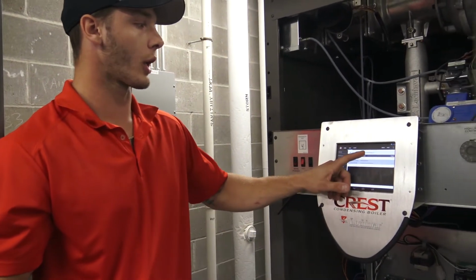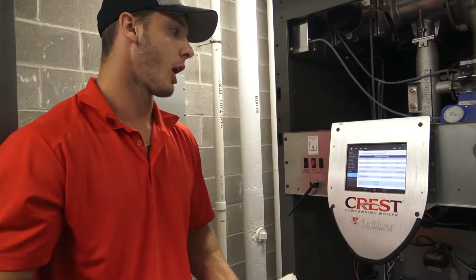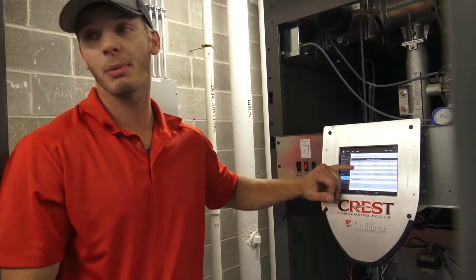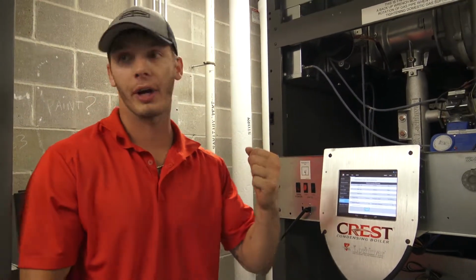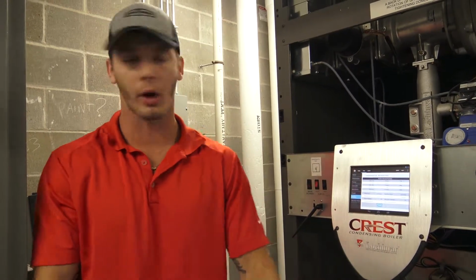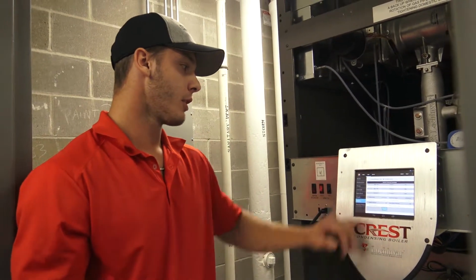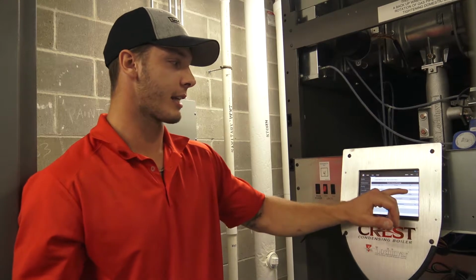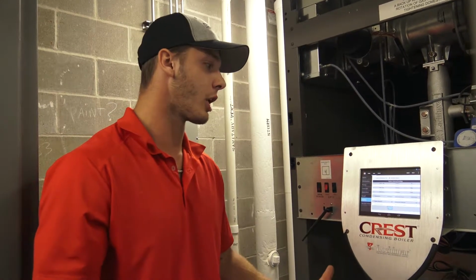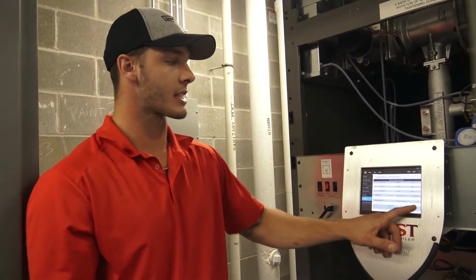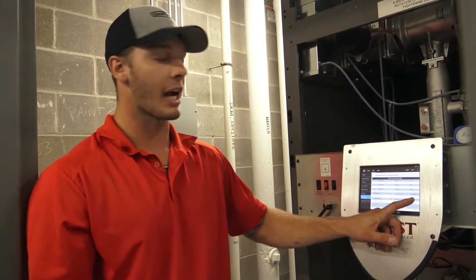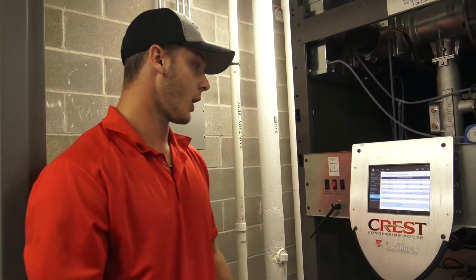And then you can also look at our runtime history. You can see how it's been firing. Has it been firing at 75 to 100% a lot? You know what I mean? Is it overrunning itself? 25 to 50%, I see 60% of the time. That's real good. I can see the total number of successful ignitions, how many times it's tried and failed, so I can come here and say, okay, was this a one-time thing, or is this a recurring issue?